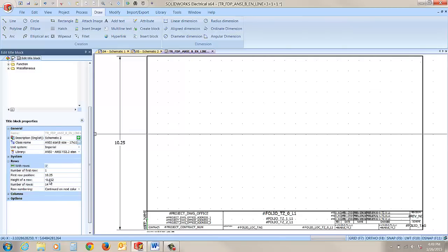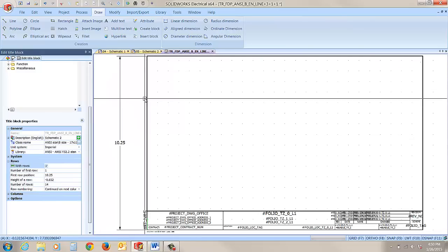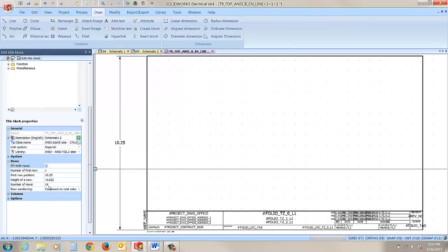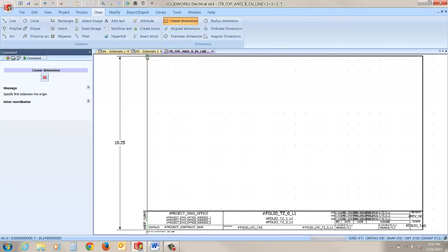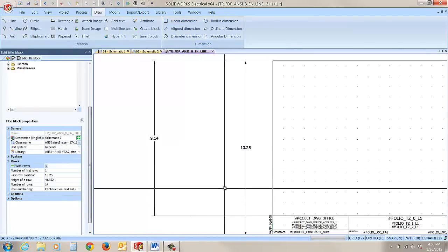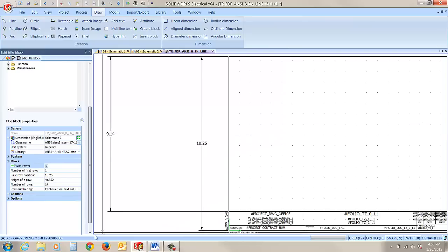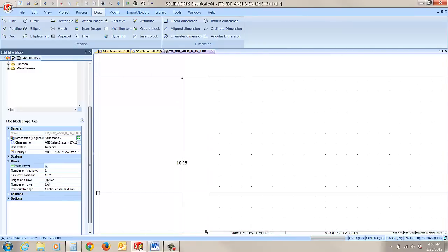And then the height of each row is at -0.652. And the reason that it's negative is that it's going to start here and go down. How I came up with this number was I knew that I wanted 14 rows. And well, I took another dimension of my usable space, which is 9.14. So then I just divided 9.14 by 14, and that gives me 0.652.